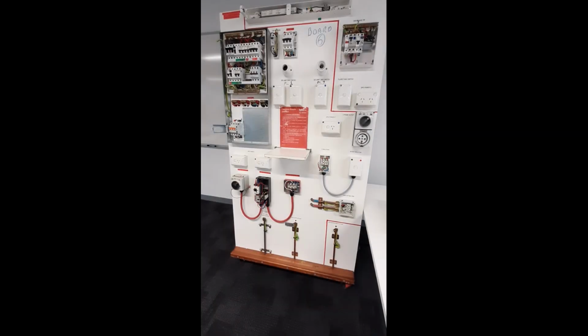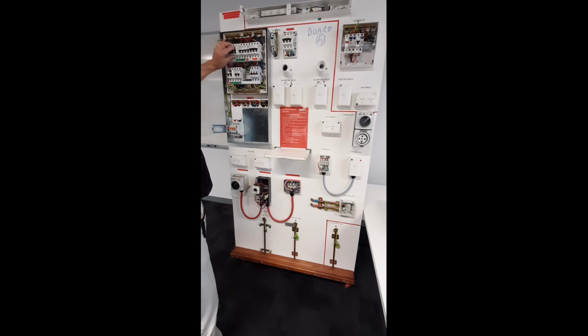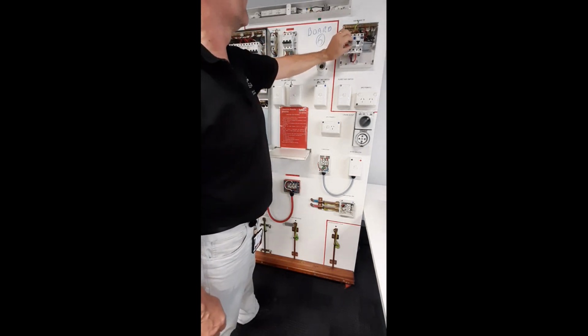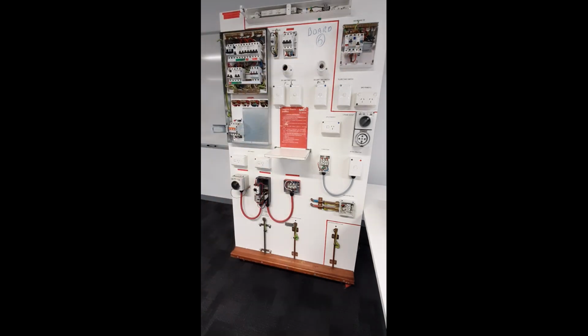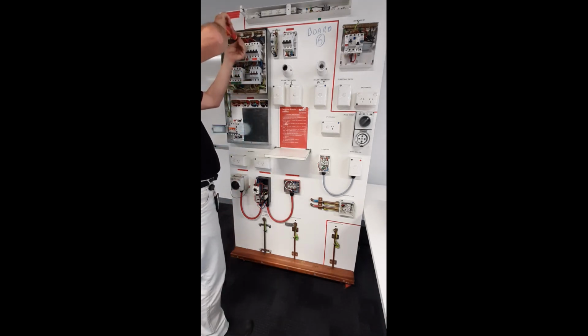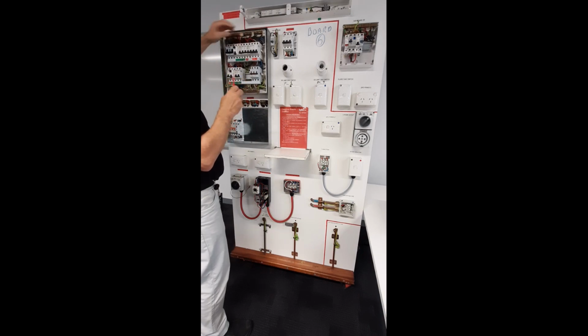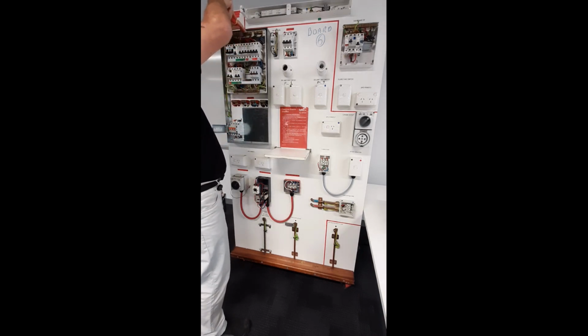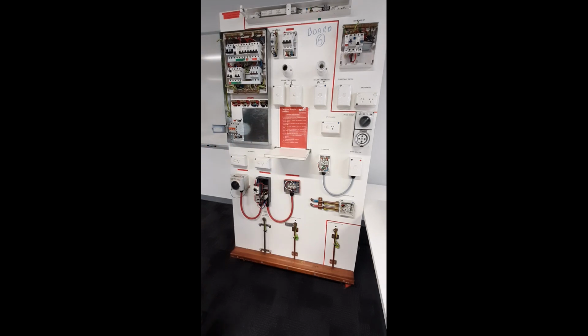Circuit setup. Ensure the supply is isolated to the electrical installation. Ensure the MEN links are disconnected at every switchboard. Turn off every main switch, every circuit breaker, and every RCD. Disconnect the active and the neutral of each circuit in turn at the switchboard. I've disconnected power circuit number 1.